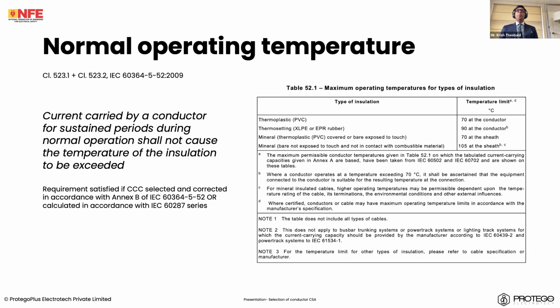When we talk about normal operating temperature, this has directly to do with the current carrying capacity. The important thing is that the current carried by a conductor for a sustained period during normal operation shall not cause the temperature limit of the insulation to be exceeded. Like I said, the important thing is the insulation. The 60364 series, the National Electrical Code of India and IS 732 are very clear on this requirement.